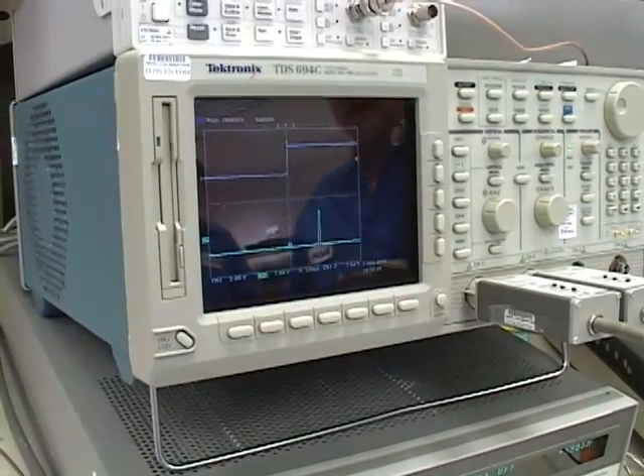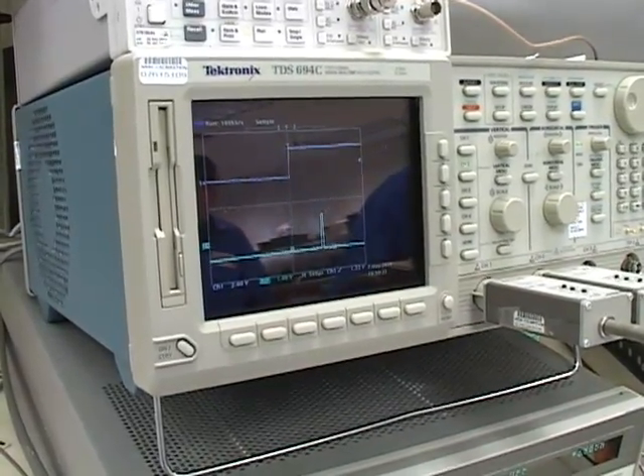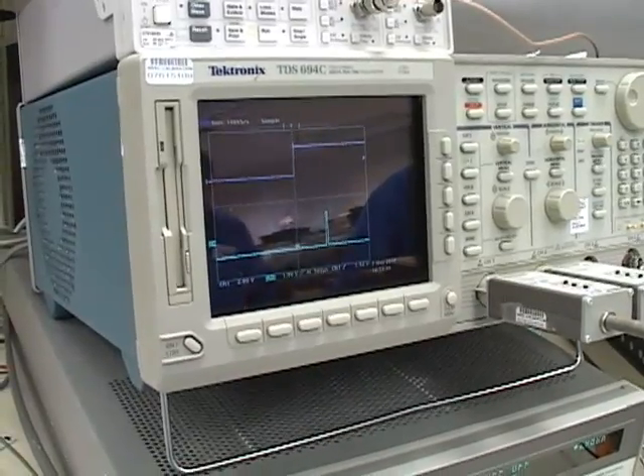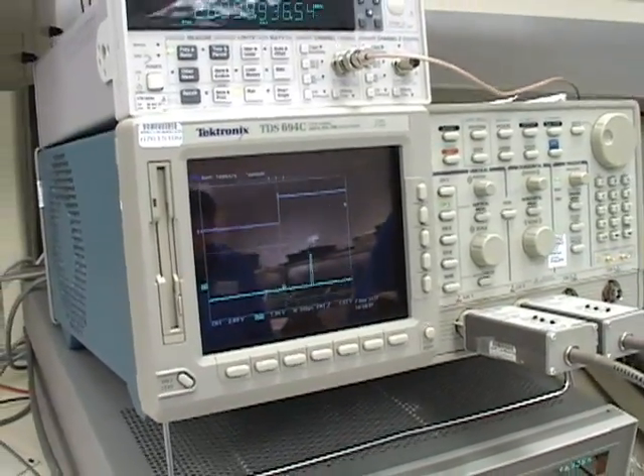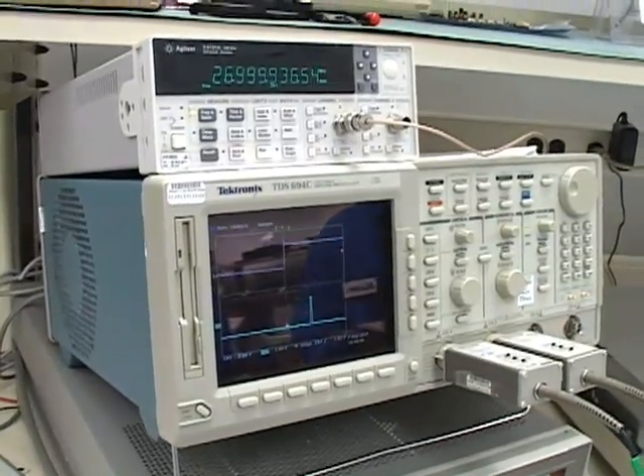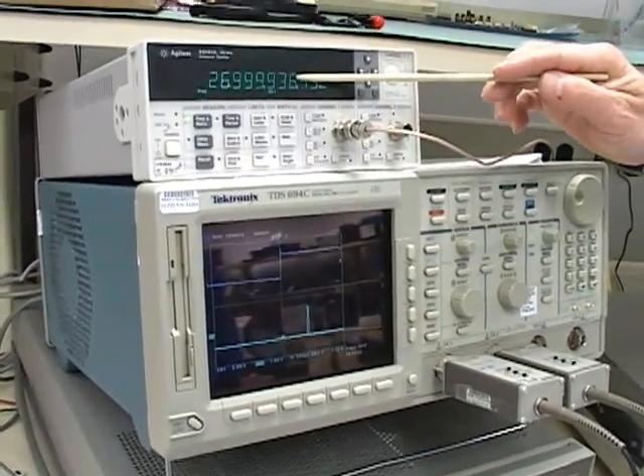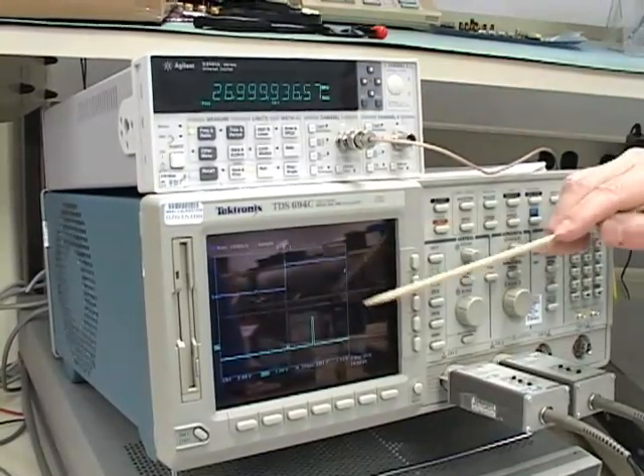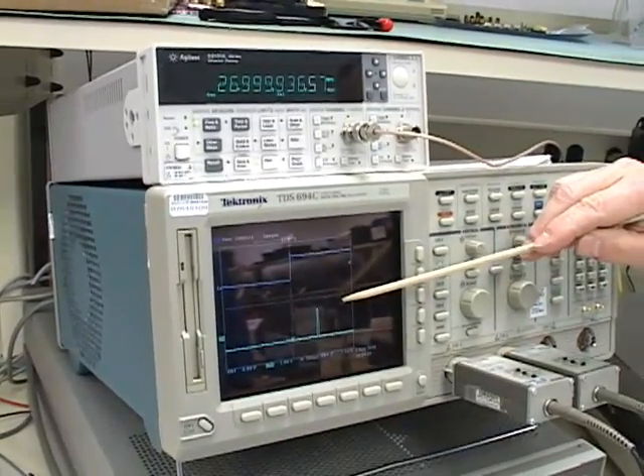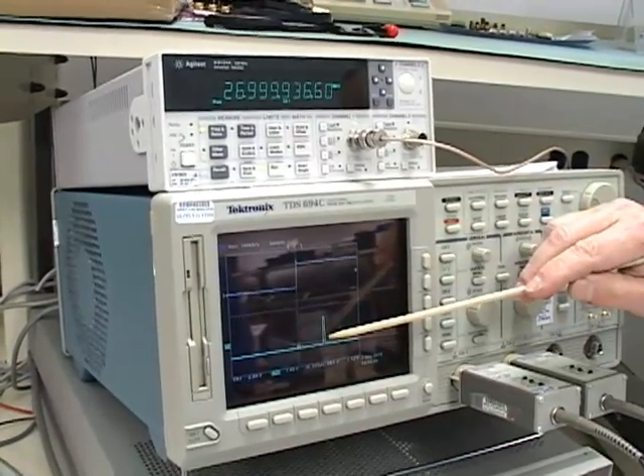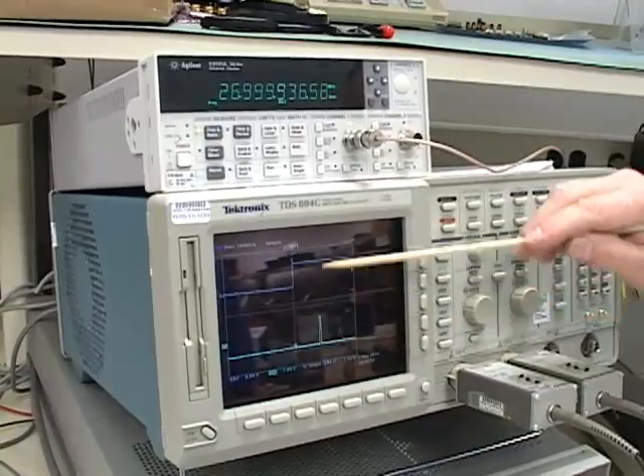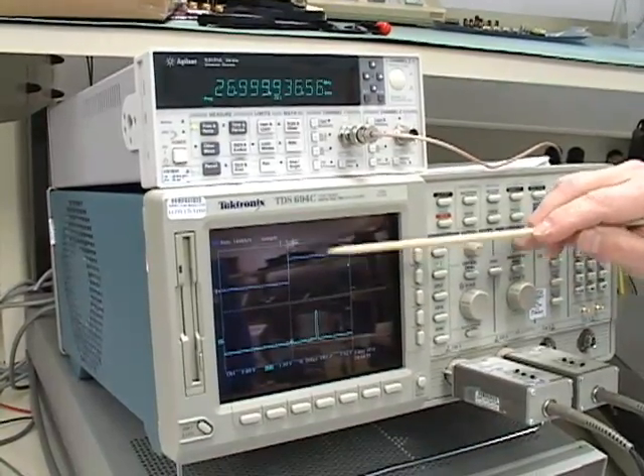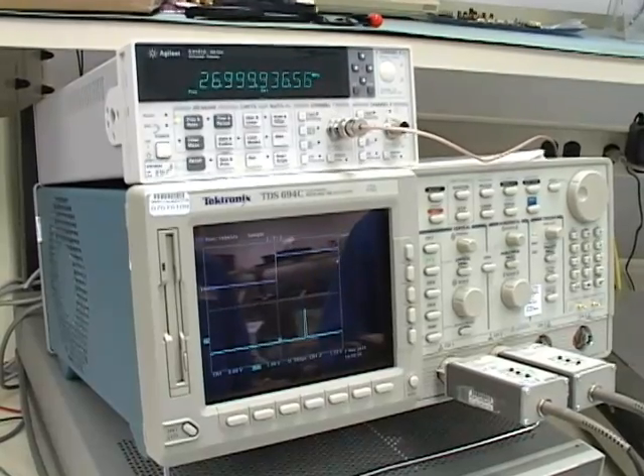Now if I put it into drift lock mode as I had it earlier, then for drift lock what will happen is now instead of just switching instantaneously it's going to skew the clock frequency. In this case it's going to skew it up which is going to result in the timing signal slowly moving back until it regains lock. When it's realigned with the input f-sync the clock frequency will go back to 27 megahertz.